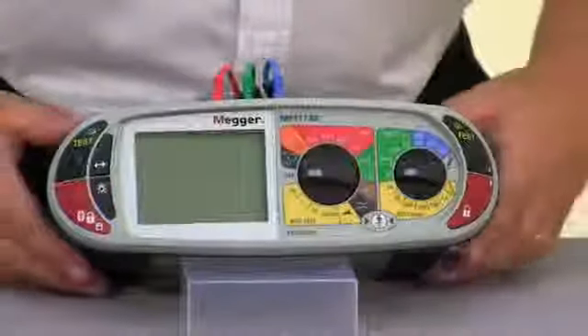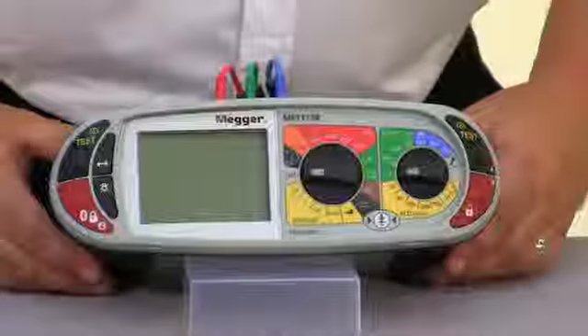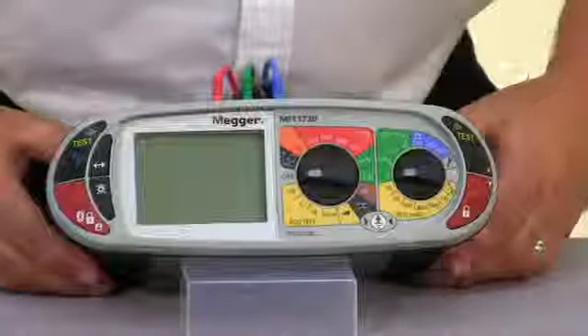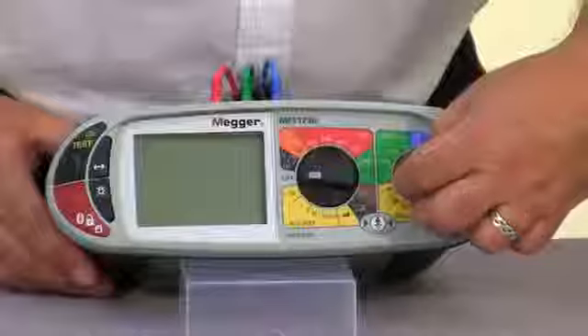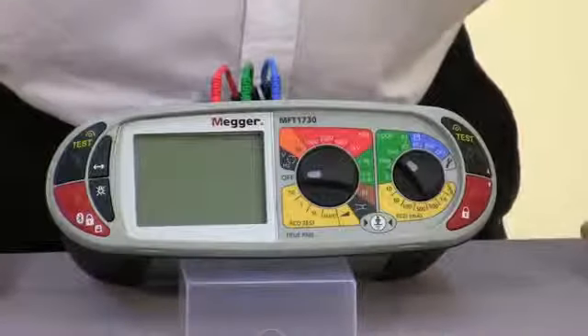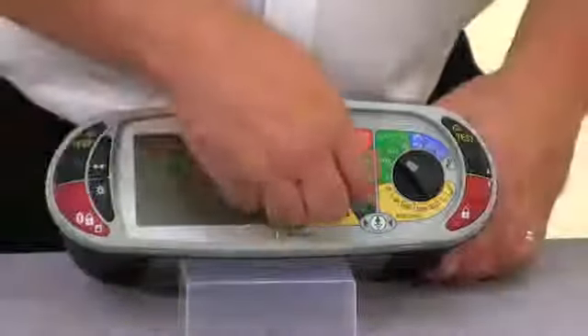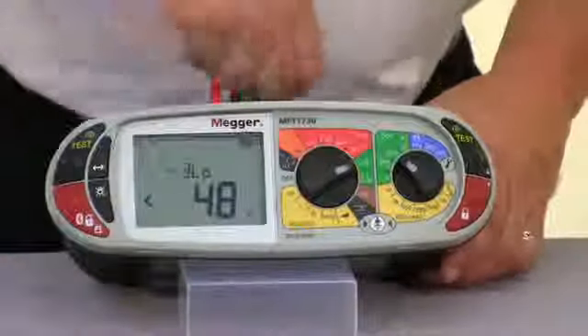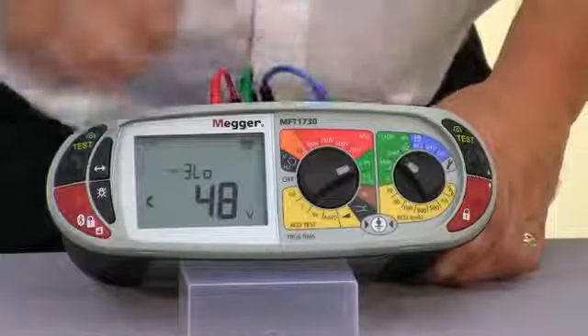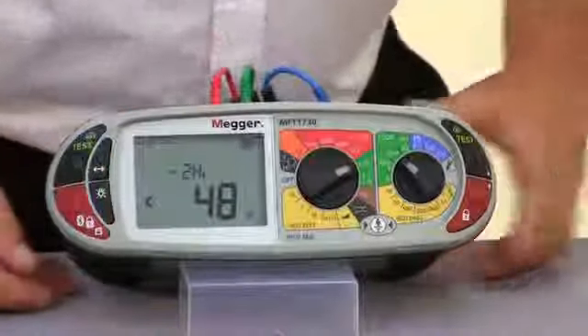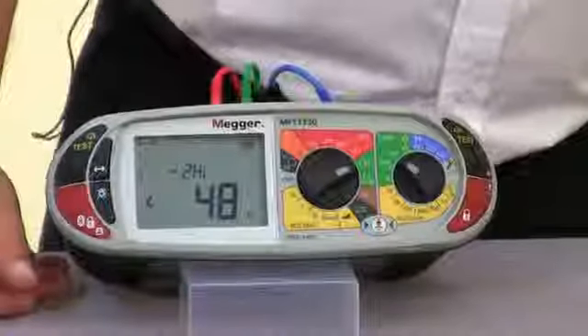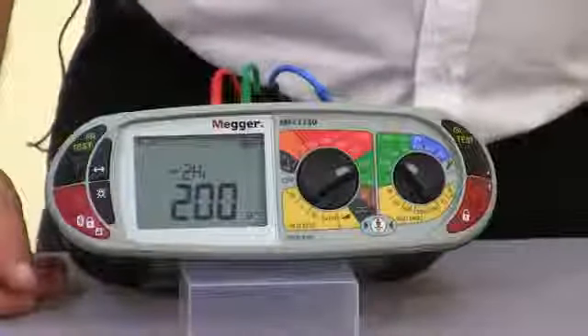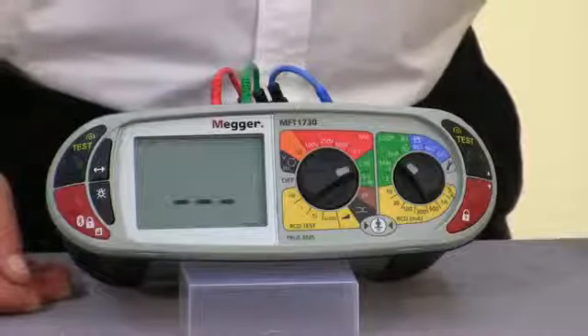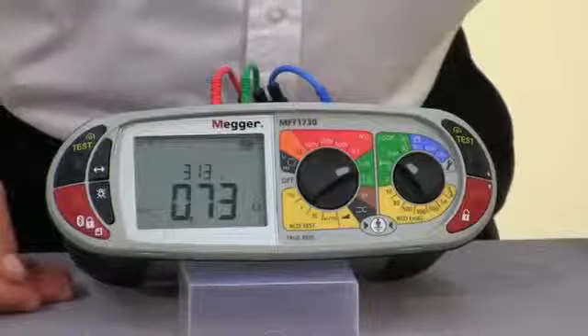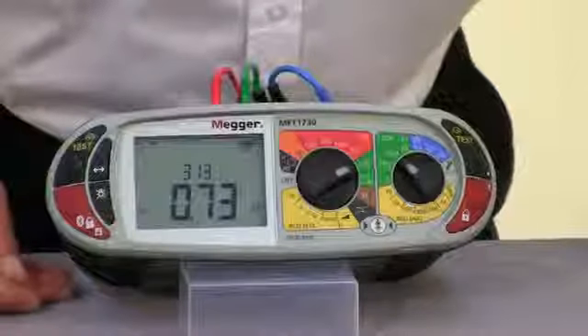Okay, and finally, on loop impedance testing, we'll look at the ZREF and R1, R2 test. The ZREF is actually our ZE, so it's a 2-wire high current test that we do at the main incomer. So selecting a 2-wire test, on the function key we apply to the circuit, the unit will auto detect and start the test, and we have a reading of 0.73 of an ohm.